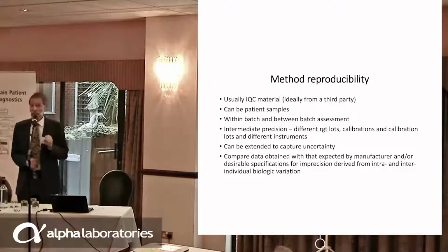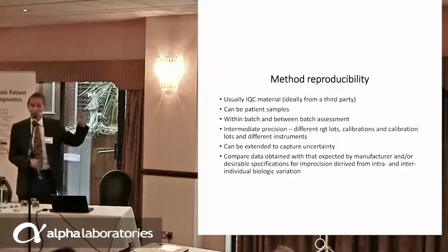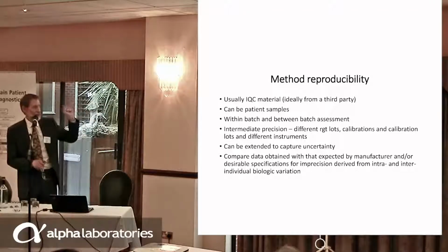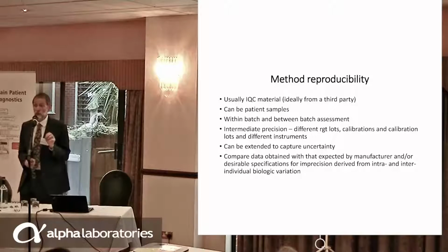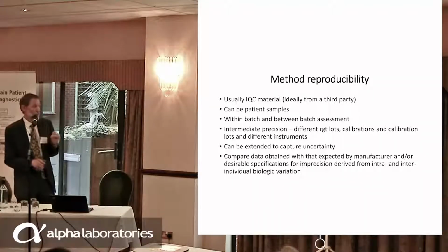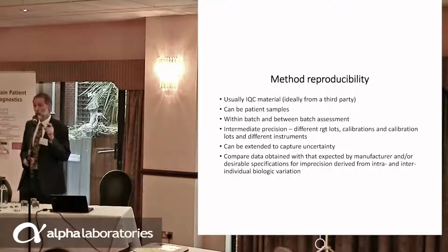Method reproducibility on IQC is generally better than it is on patient samples. So I think the complexity of matrix of patient samples makes them a little bit more ideal, but I accept that most people would use the IQC material. I think there needs to be some sort of assessment within and between batches, and when you're introducing a method, that's what you need to put in.